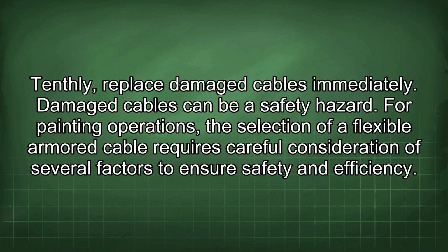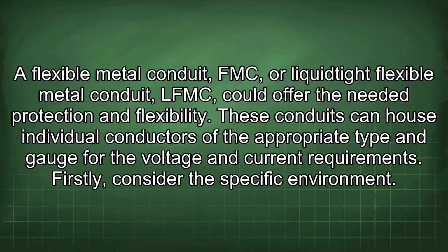For painting operations, the selection of a flexible armored cable requires careful consideration of several factors to ensure safety and efficiency. A flexible metal conduit (FMC) or liquidtight flexible metal conduit (LFMC) could offer the needed protection and flexibility. These conduits can house individual conductors of the appropriate type and gauge for the voltage and current requirements.